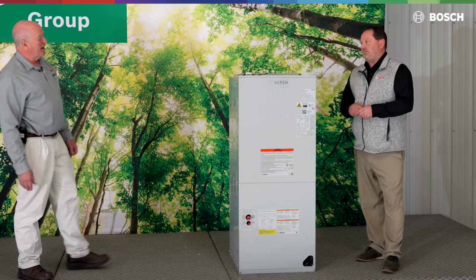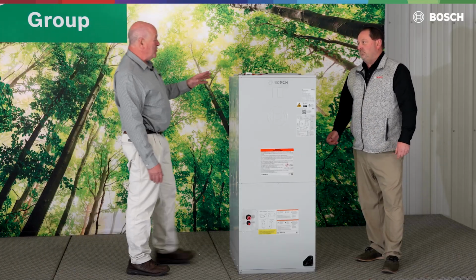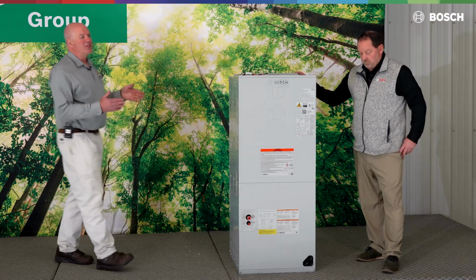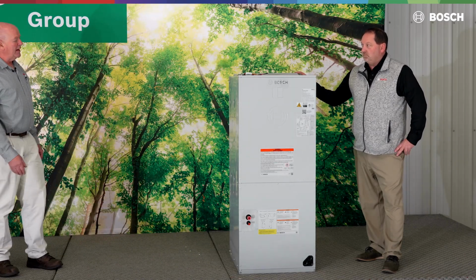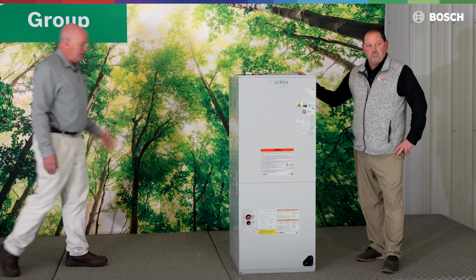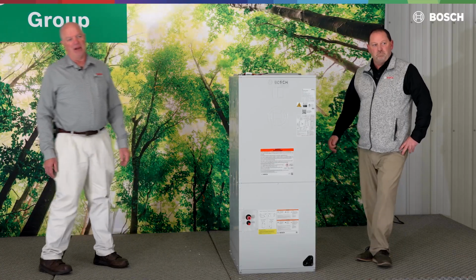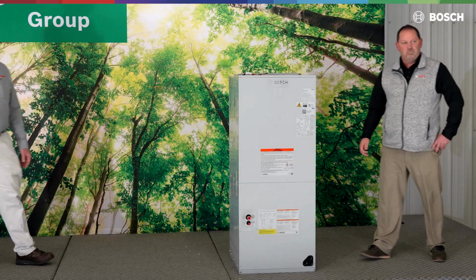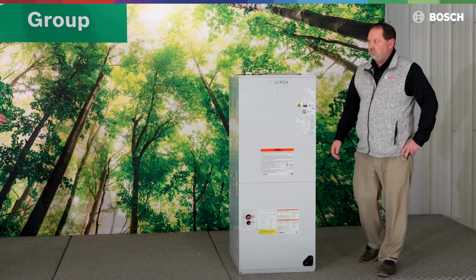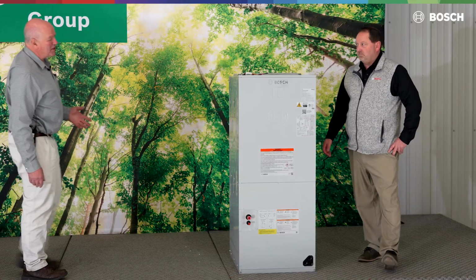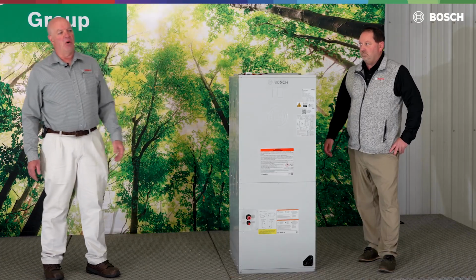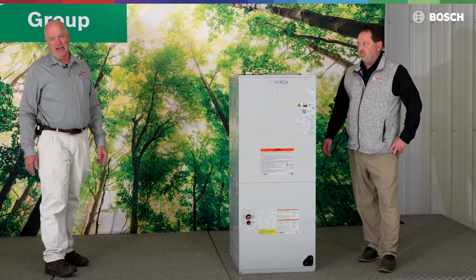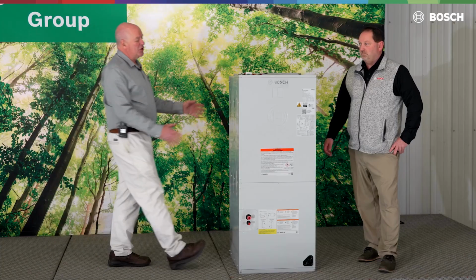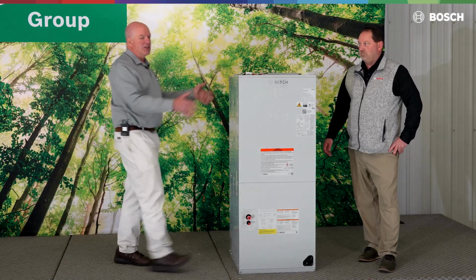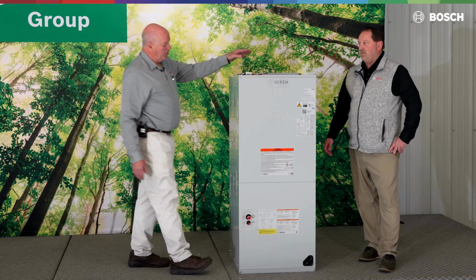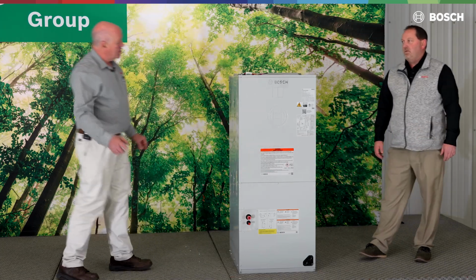You know, Chris, one of the other things that come up sometimes, we have a lot of issues down in the Florida location where they'll mount these into a garage space. And because they do really great dehumidification and cooling, the units will tend to sweat. So there are some regulations that recommend that we never install this over an 86-degree location. So if you're going to choose this in Florida in the garage, it's 95 degrees in there and 80% relative humidity or above, it will sweat, it will condensate.